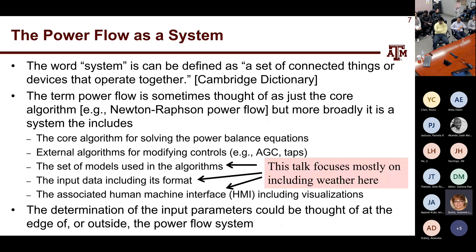The word 'power flow' can be used in different ways. In its most specific sense, it's just the core algorithm — like Newton-Raphson power flow taught in an undergrad class. More broadly, it includes external algorithms for automatic generation control, tap control, and similar functions. Even broader, it includes the models that go into it, the input data, and the human-machine interface including visualizations. This talk mostly focuses on bringing additional models and data in, not modifying the core algorithm.